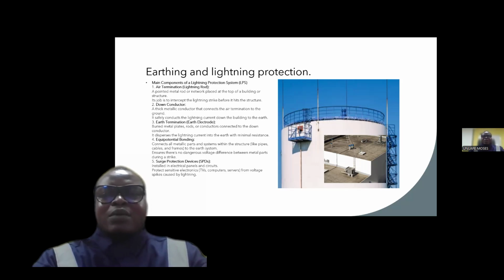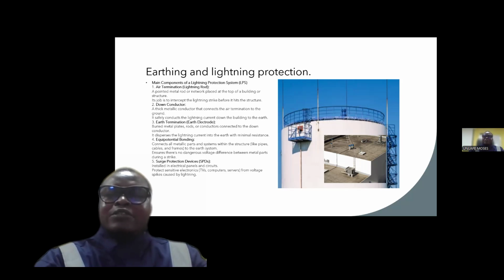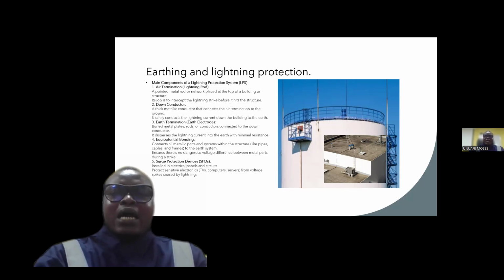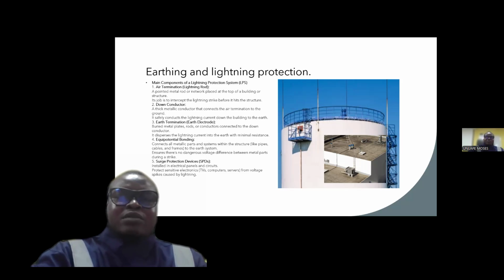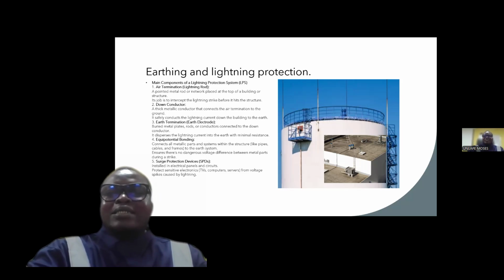Then we also have the grounding system. This grounding system functions by dissipating all electrical energy from lightning into the earth, and the components are grounding rods and plates. That is why it is used in substations, telecommunication towers, and residential buildings. And above all, we have the surge protection device, which is SPD. The surge protection device protects all electrical appliances from voltage surges due to lightning. We have different types of surge protection. We have type 1, which is for the main panel. We have type 2, which is for the distribution board. We have type 3, which is for individual devices. Each of them is installed at homes, data centers, and industrial control panels.